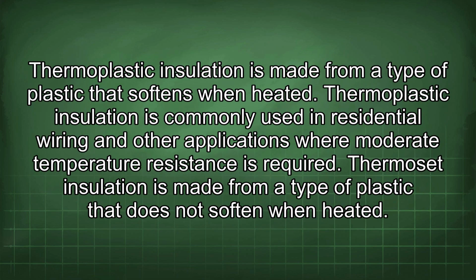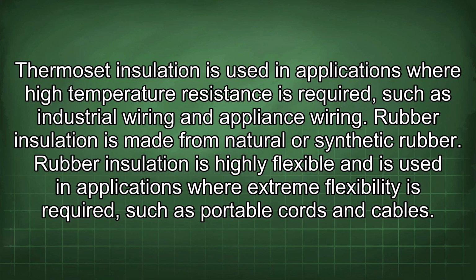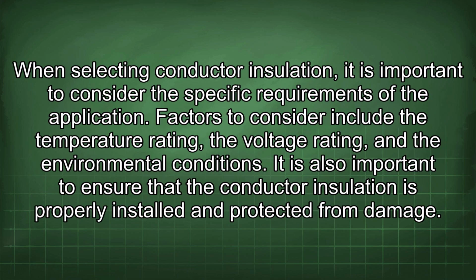Thermoplastic insulation is made from a type of plastic that softens when heated. Thermoplastic insulation is commonly used in residential wiring and other applications where moderate temperature resistance is required. Thermoset insulation is made from a type of plastic that does not soften when heated. Thermoset insulation is used in applications where high temperature resistance is required, such as industrial wiring and appliance wiring. Rubber insulation is made from natural or synthetic rubber. Rubber insulation is highly flexible and is used in applications where extreme flexibility is required, such as portable cords and cables. When selecting conductor insulation, it is important to consider the specific requirements of the application.